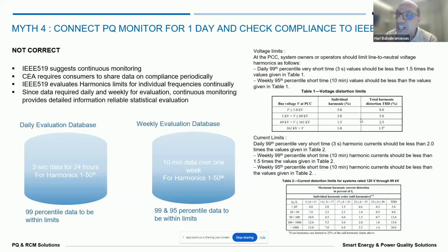Then, connect a PQ monitor for one day and check the compliance for IEEE 519. No, as I said, that's a myth. I cannot do power quality monitoring for one day, do a power quality study, and say I am complying with the standard or not. We have to take three kinds of statistical evaluation: one for daily and weekly values, 95 percentile and 99 percentile, which is defined in the standard. So for the IEEE 519 measurement to be completed, we need 7 days of daily values and then 1 week of values to completely comply. You will have 7 days of pass or fail for the daily values, and then weekly values as well, taken every 10 minutes, to determine whether it is pass or fail as per the limits. So this is just a small piece of information which I thought I should give.